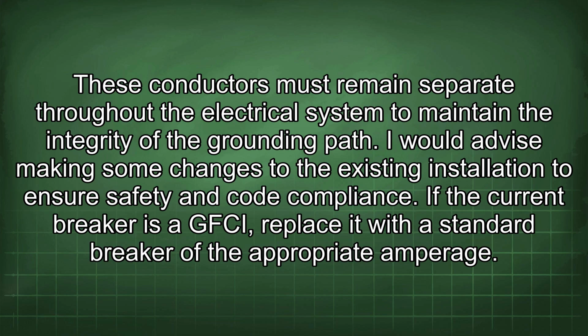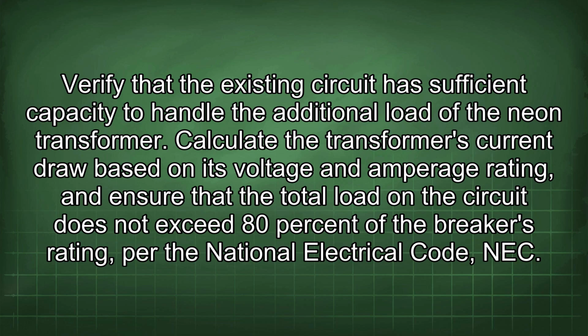I would advise making some changes to the existing installation to ensure safety and code compliance. If the current breaker is a GFCI, replace it with a standard breaker of the appropriate amperage. Verify that the existing circuit has sufficient capacity to handle the additional load of the neon transformer.